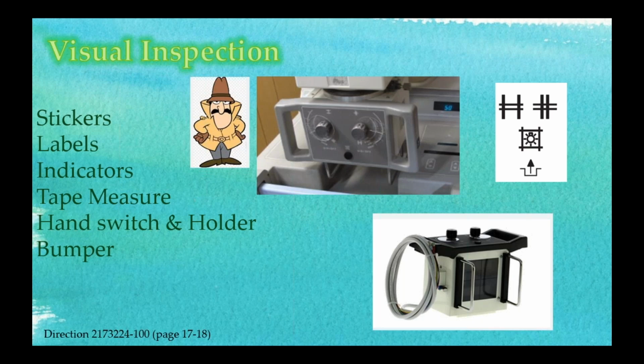And basically, it's going to tell you your source to image distance. Source is the x-ray tube, image is where the plate is. So there's a specific controlled distance there for the type of anatomy. The x-ray techs know it. The numbers on the dial here are set to a 40-inch source to image distance. If I do it at 35 inches and I try to measure the x-ray field that I just produced, and I have my collimator knobs at, let's say, 24 by 24, it's not going to be accurate, because those dials are set and calibrated at a certain source to image distance.